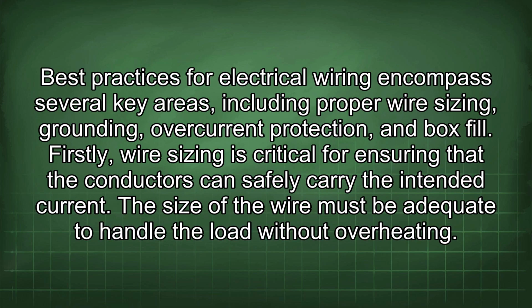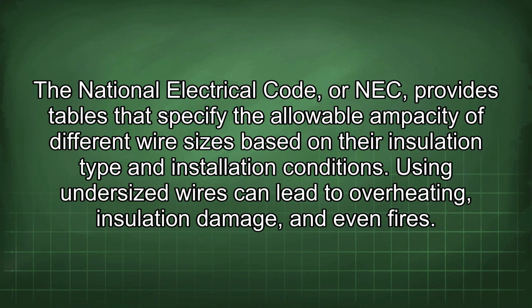Best practices for electrical wiring encompass several key areas, including proper wire sizing, grounding, overcurrent protection, and box fill. Firstly, wire sizing is critical for ensuring that the conductors can safely carry the intended current. The size of the wire must be adequate to handle the load without overheating. The National Electrical Code, or NEC, provides tables that specify the allowable ampacity of different wire sizes based on their insulation type and installation conditions.